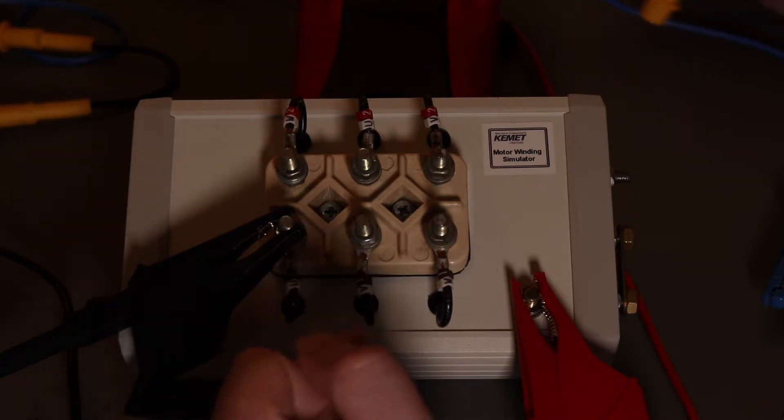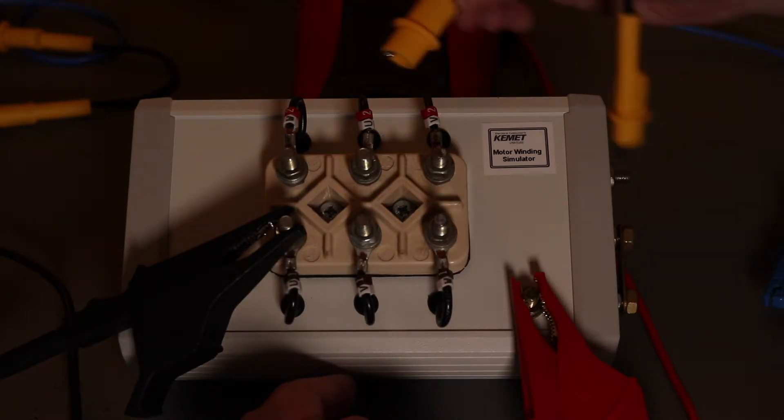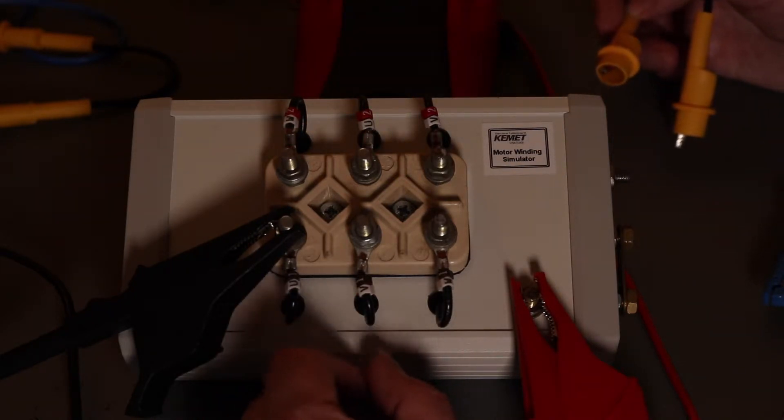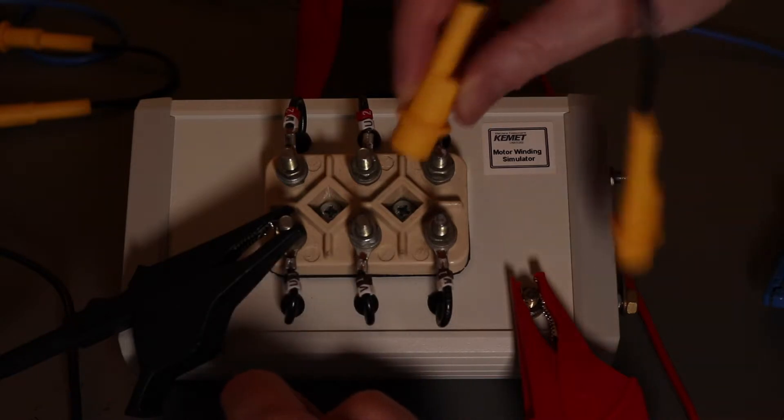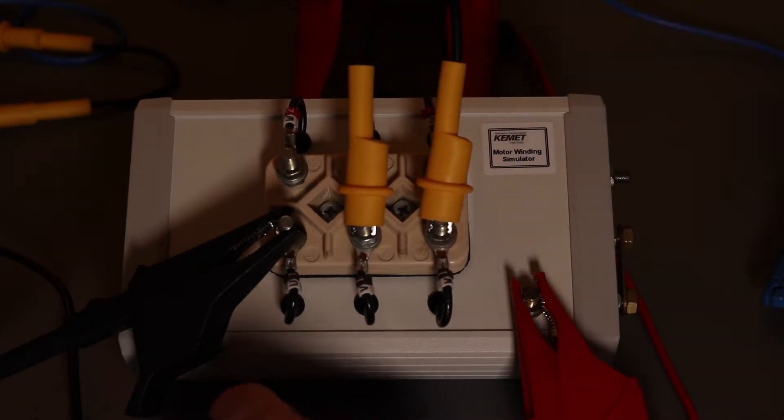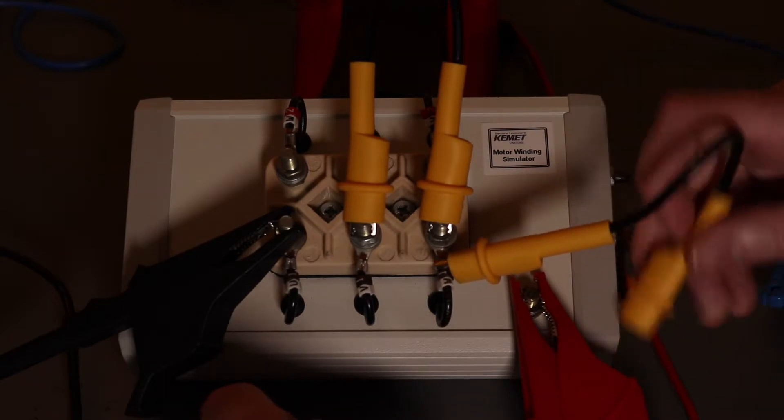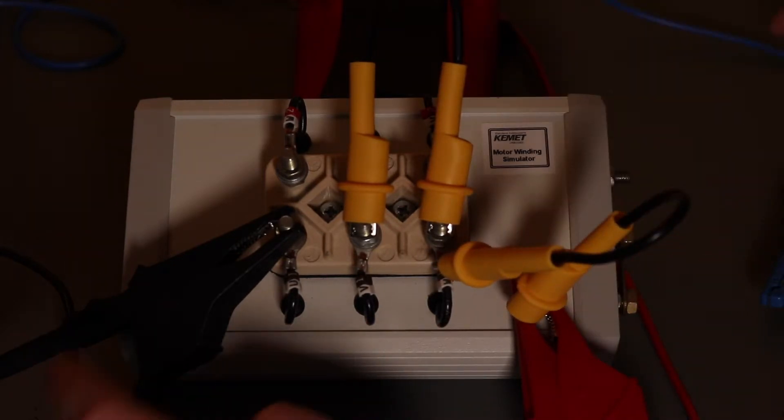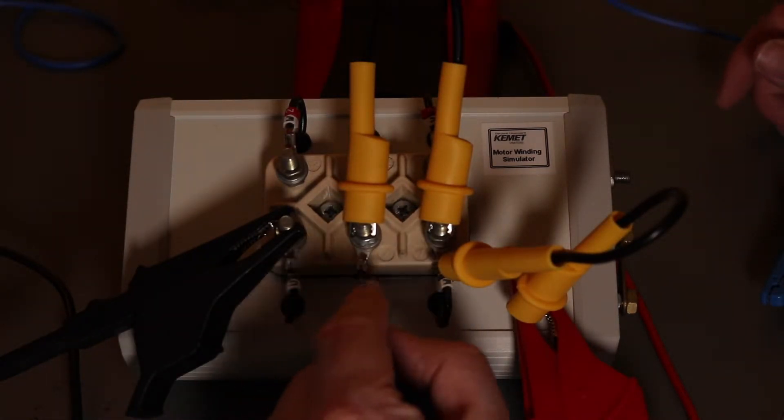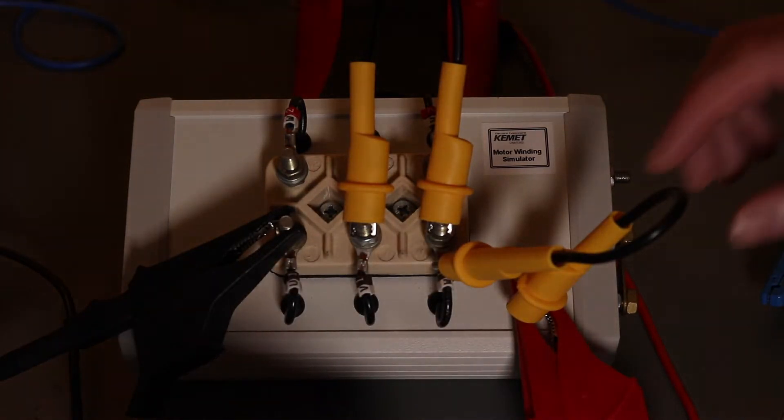This is my motor simulator setup. As you notice at this moment I've got no links across so I've got the ability to test each phase individually. When I would normally do that, I would link the two untested phases with another link and take them to earth. So then any leakage from this phase to earth is measured plus the leakage from this phase into either of these two phases, and then into earth, and I get a total insulation resistance reading.